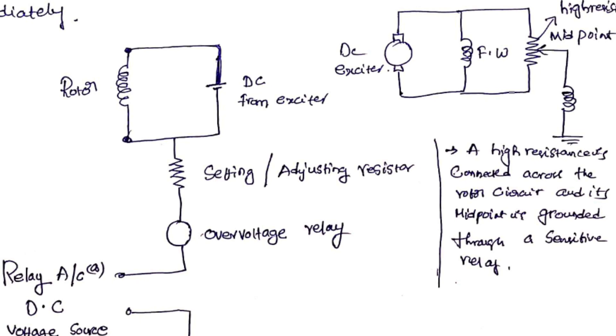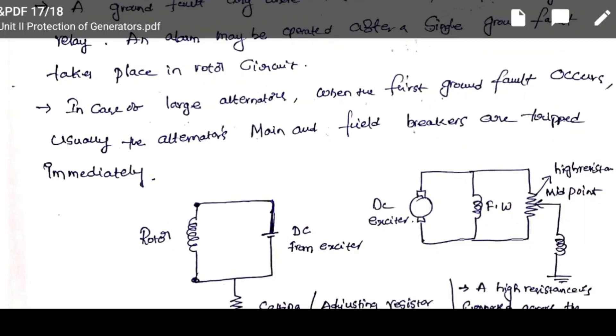We have to identify the fault and the rotor will be protected. Whenever the first ground fault occurs, usually the alternator's main and field breakers are tripped immediately. When the alternator is large, upon occurrence of a ground fault, the main field winding breakers are tripped.